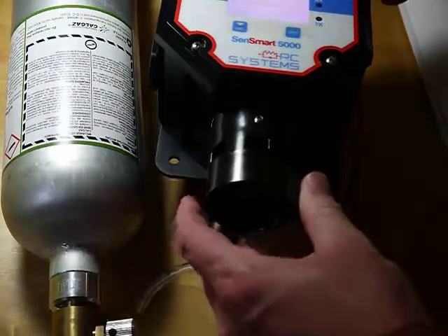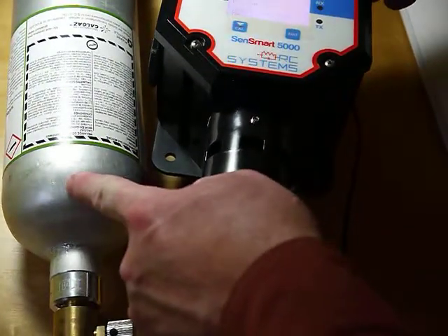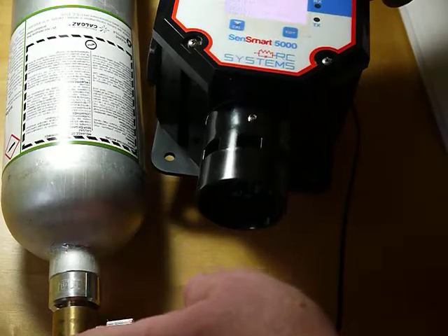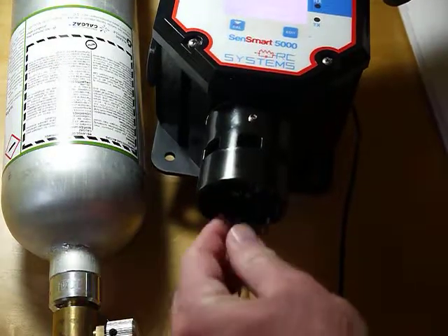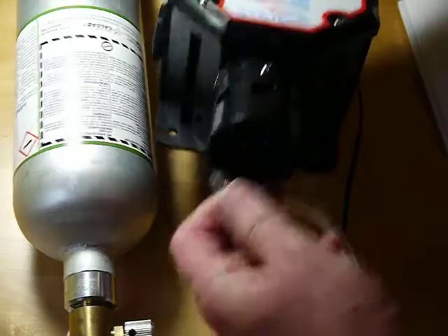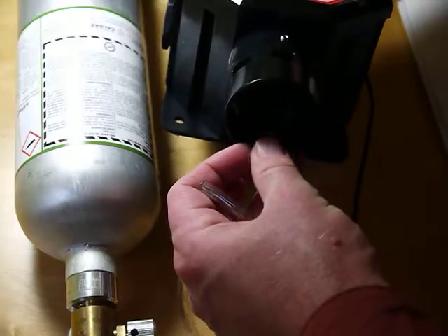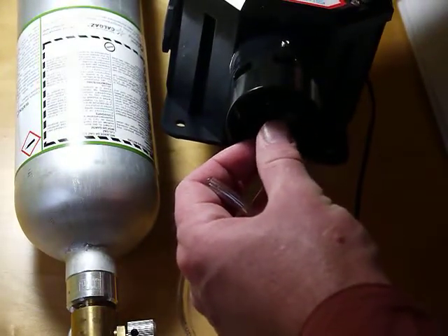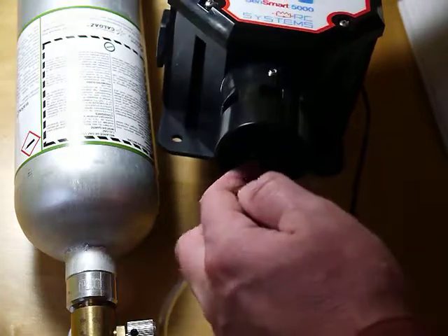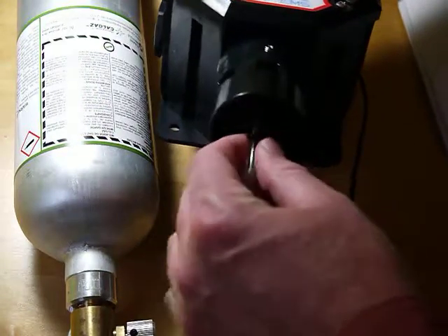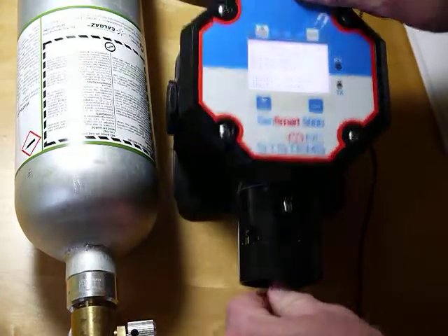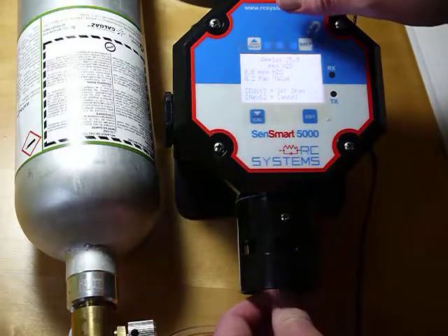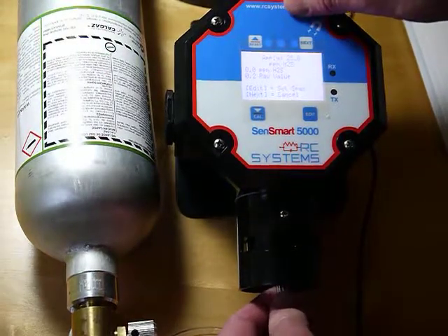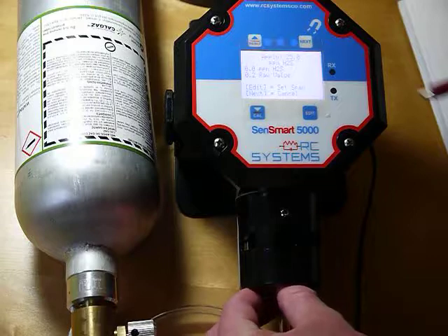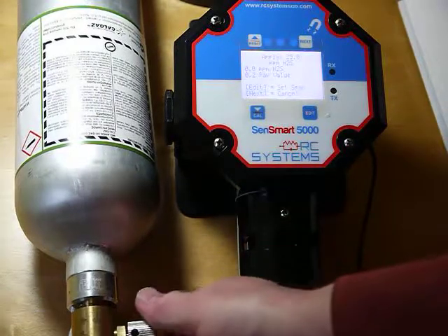So I've got my cylinder of 25 ppm H2S, a regulator. The regulator I'm using is 0.5 liters per minute. The fitting on this particular transmitter has this calibration point right here, so I can just connect directly to it with the hose. Some of the other transmitters, you'd need a cup or some way to get the gas onto the sensor without pressurizing it. Okay, so I'm going to start the flow.